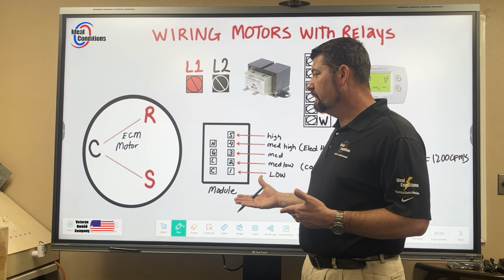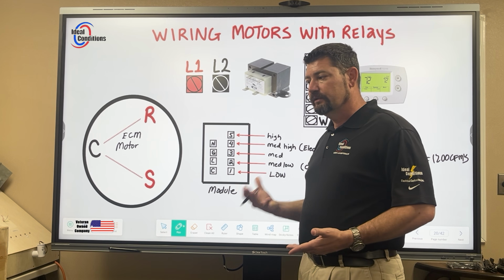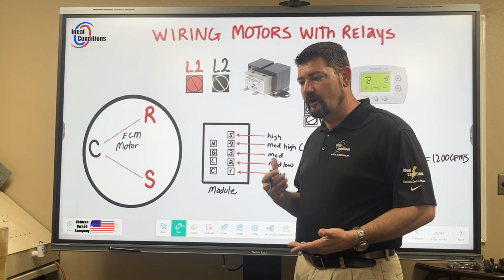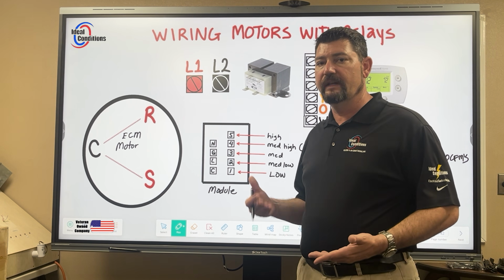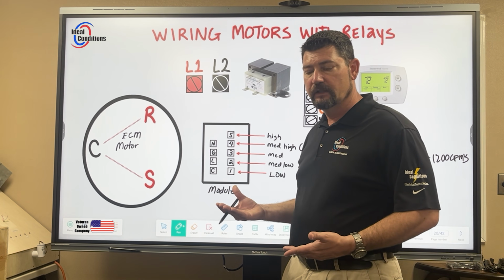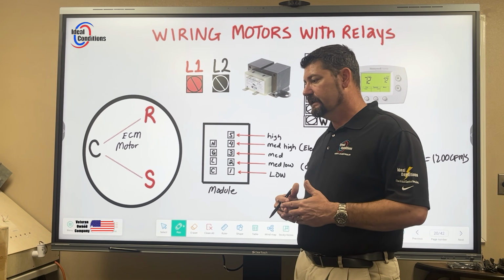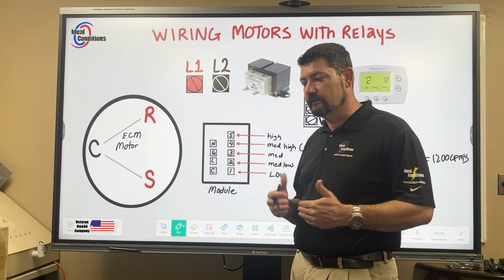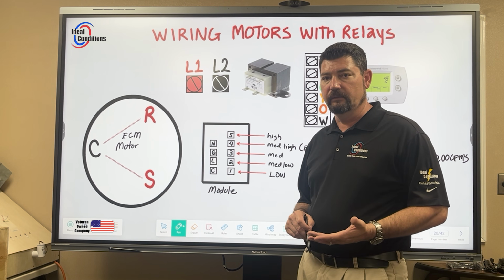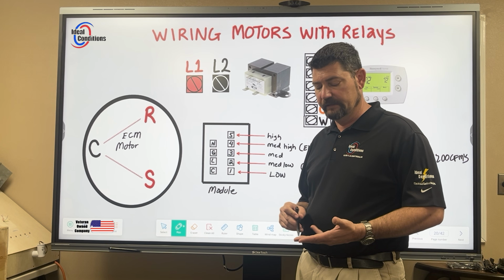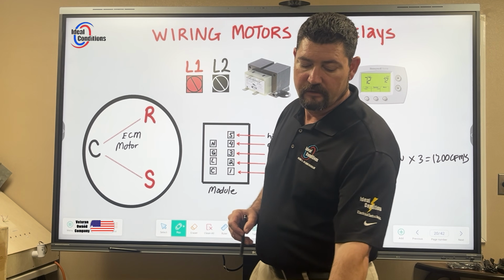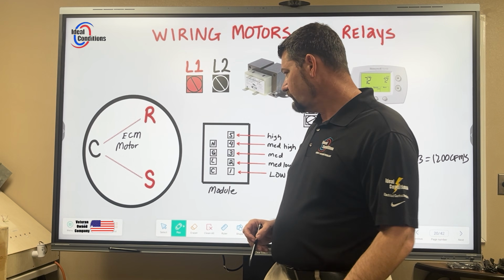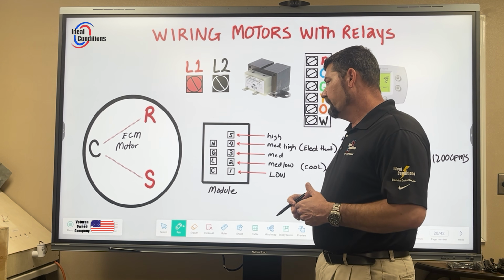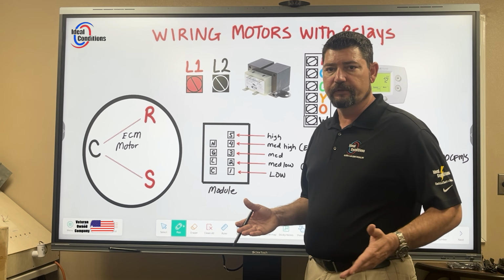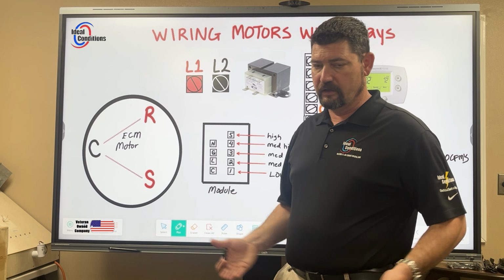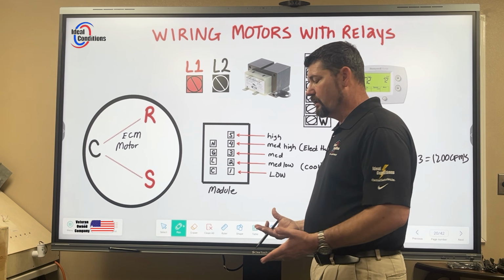And so if your motor has failed and you just replace the motor, if you don't find out what caused that motor to fail, then that motor will fail again. You can't blame it on voltage. You can't blame it on a lot of things that don't make sense. You have to start looking at other things. Is my coil clean? Okay, is it wired properly? Are my connections good? Do I have faulty connections? Do I have poor airflow across filters because they're not being changed often enough, and that's causing problems? Do I have improperly sized ductwork?